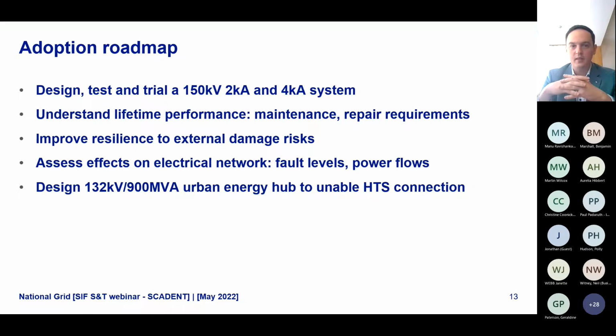This creates a market where more HTS systems can be used at certain power ratings, similar to how we use ratings for transformers — there are certain typical ratings for circuit breakers. That's what we'd like to achieve: a certain standard design for a certain standard rating, so networks from around the globe can use the technology.